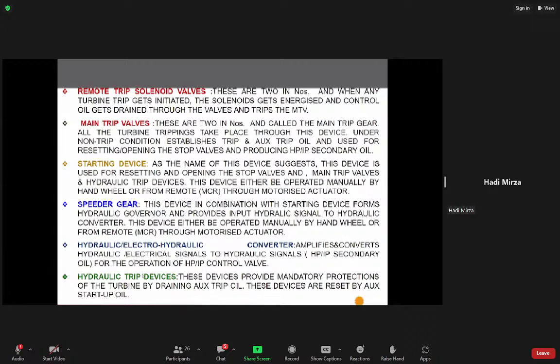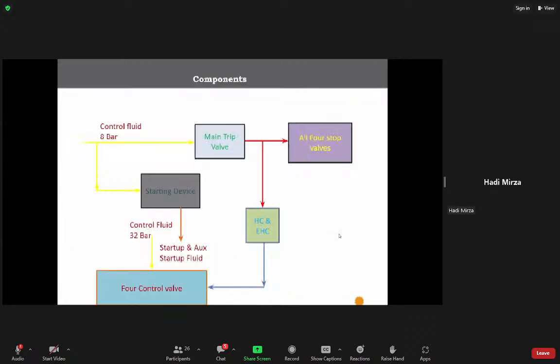Hydraulic trip devices. These devices basically hold the auxiliary trip oil pressure until and unless any trip command comes to them, or if there is an overspeed trip mechanically, if RPM increases, then also this device will operate and trip the unit. For resetting these auxiliary hydraulic trip devices, startup oil is used.